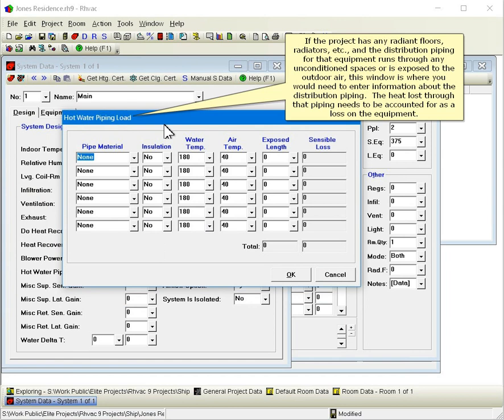If the project has any radiant floors, radiators, etc., and the distribution piping for that equipment runs through any unconditioned spaces or is exposed to the outdoor air, this window is where you would need to enter information about the distribution piping. The heat lost through that piping needs to be accounted for as a loss on the equipment.